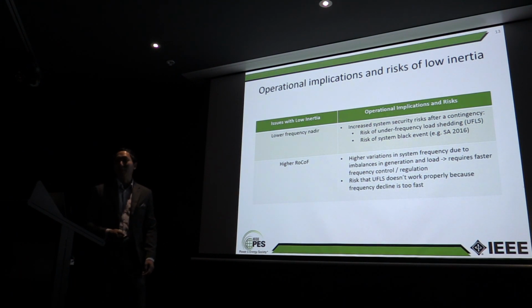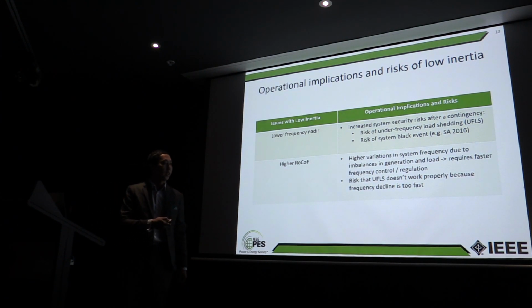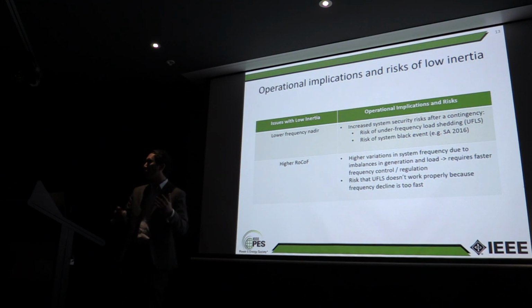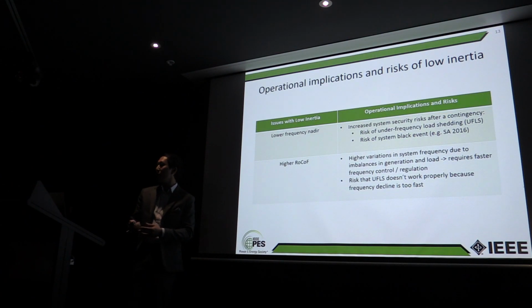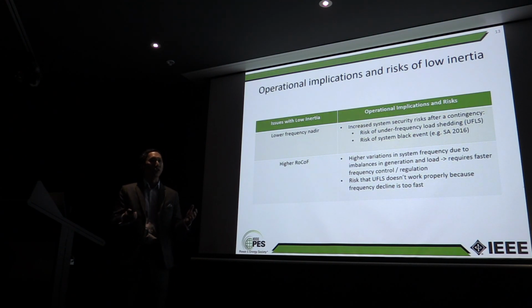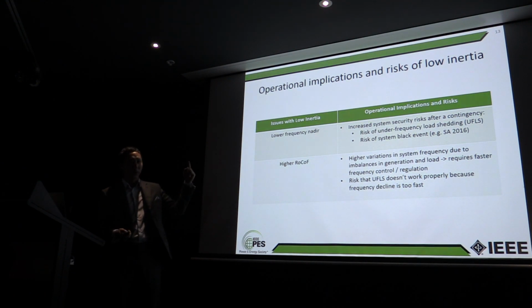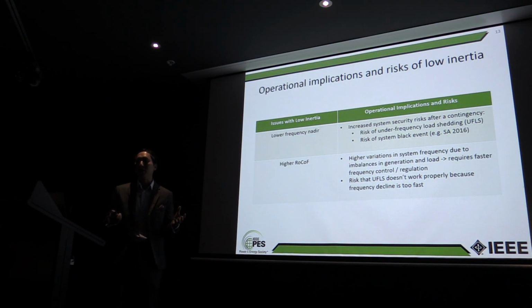And the other risk is that we can have a system black event, a blackout, which is basically what happened in South Australia. If you remember, in 2016, they had a couple of tornadoes hit a few lines and took out those lines, and happened to take out a few wind generators. There were some protection issues with the wind generators, and they went off, and then that overloaded the interconnector from Victoria. And then that one went off, and basically you just had a lot of load and not much generation. So the frequency went down very quickly, and blacked out the whole system. That's the risk of that kind of event. And it was a low inertia system, because once it was islanded, there wasn't that much generation in South Australia itself. It was a very low inertia system.